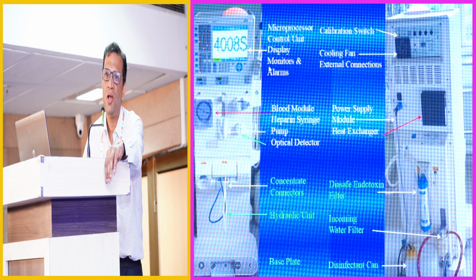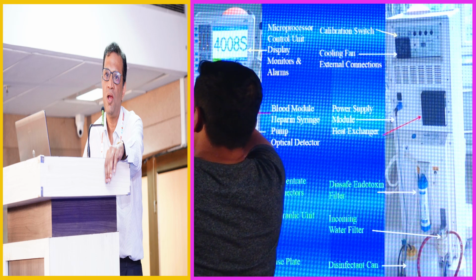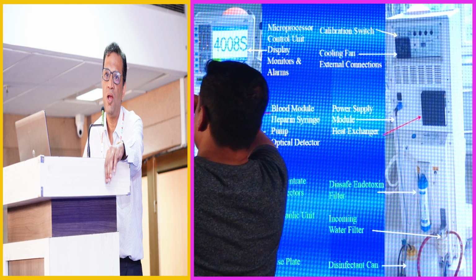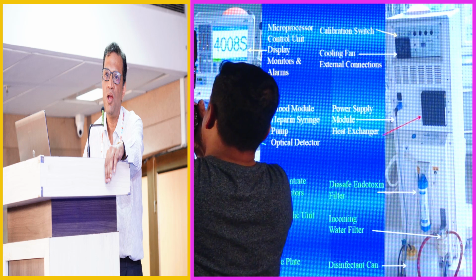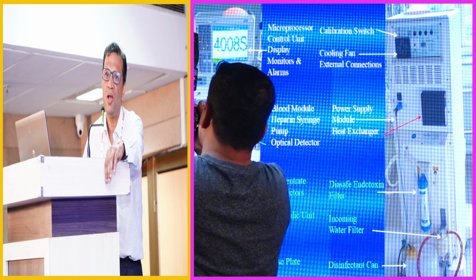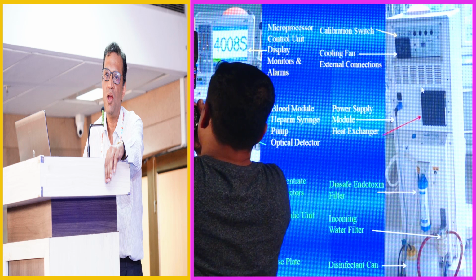The design of this machine is pretty good. At the top of the machine, you have the microprocessor unit and an LCD display. Below that, what you have here is the blood pump with the various pressure port monitors. There is a lot of talk about pressure since this morning. And at the back of the machine, in the corresponding area, you have the machine's power supply. And in the base of the machine, you have the hydraulic unit.